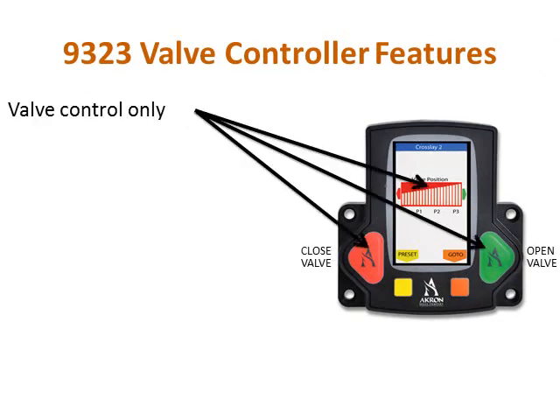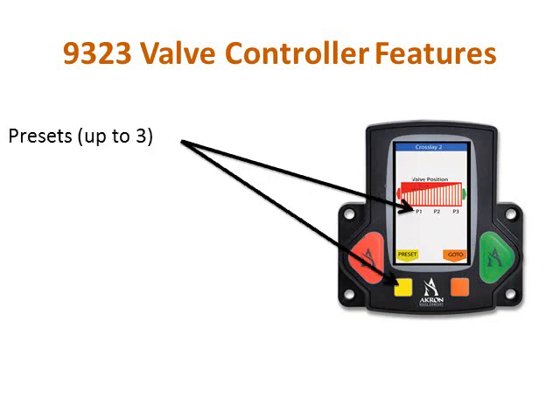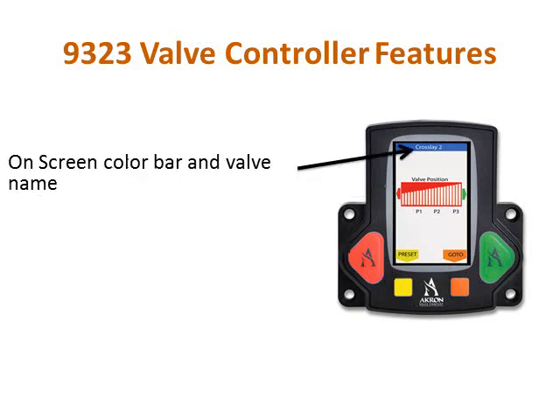The Style 9323 valve controller allows the user to open and close the valve while monitoring the valve position on the screen. It also has preset functionality built in. Preset valve positions can be saved, and then the valve can be sent back to a preset position at any time using the preset button. Another new feature available is the option to display the name of the valve on the top of the screen. Pre-programmed names can be chosen and displayed in this bar. The valve color can also be selected, and the top of the screen will display the color of the line.